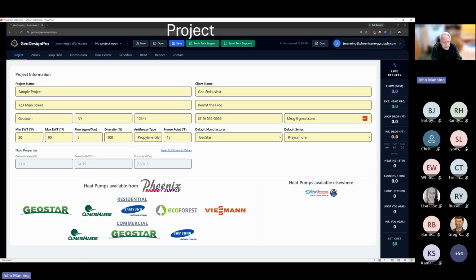And although heat pumps are rated at 3 GPM per ton, I think you can benefit your overall design by considering as low as 2.25 to 2.5 GPM per ton, which is fundamental to a lot of the work that Steve has done. You can also incorporate diversity factors to help in gauging the pump and the pressure drops of your system. Antifreeze, we offer propylene, methanol, and ethanol choices. You can specify the exact freeze point you're looking for, and the program will calculate the required concentration.